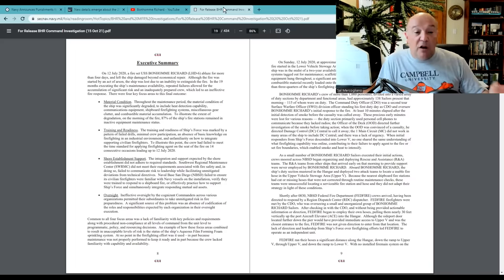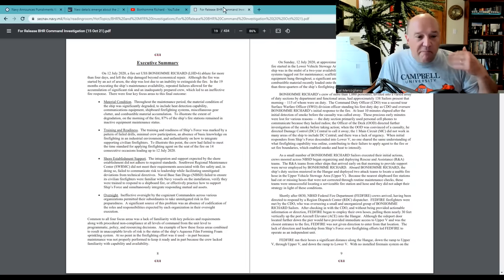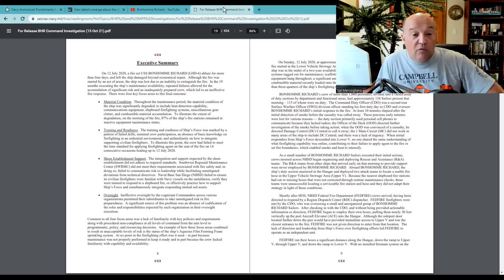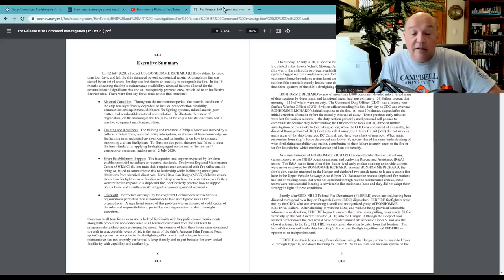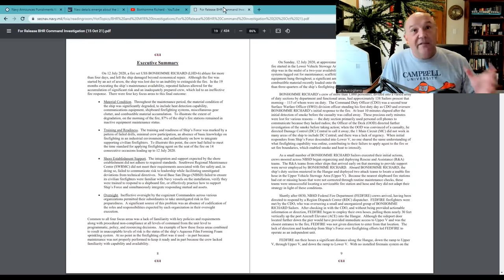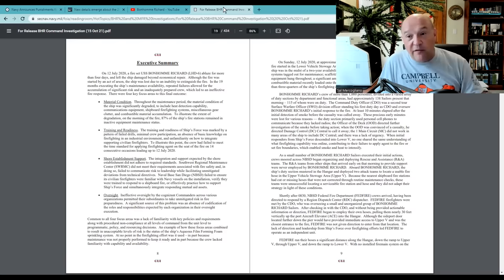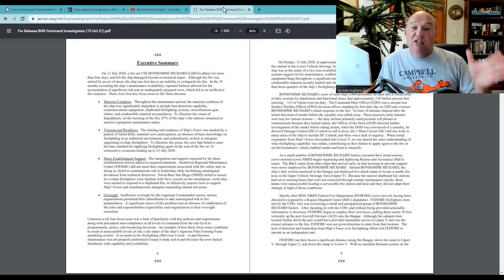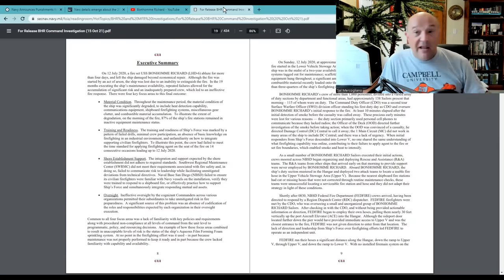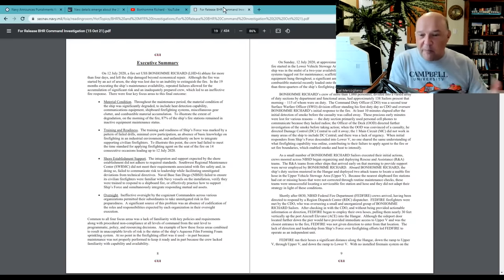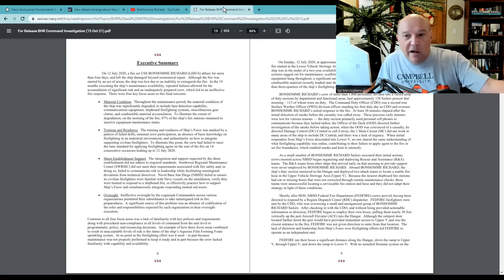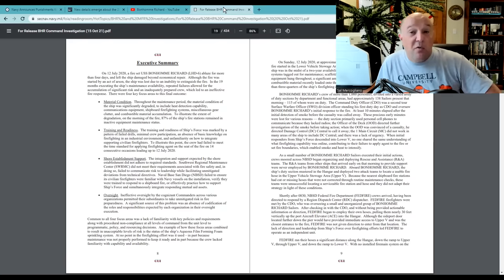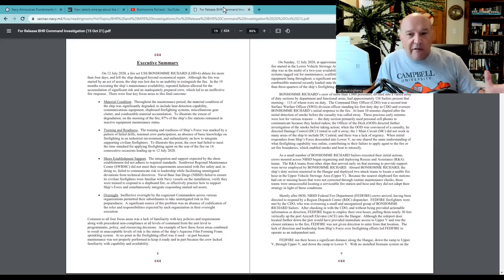Shore establishment support. The integration of the shore base with the ship failed on a massive basis. The Southwest Regional Maintenance Center did not meet the requirements associated with fire safety, and in doing so, failed to communicate risk to leadership while facilitating unmitigated deviations from technical directives. The Federal Fire Department didn't have adapters to connect their firefighting equipment to the ship's firefighting equipment, nor did they have provisions in place to lay fire hose from their rigs on the pier, their fire engines on the pier, into the ship. They didn't even have a fire main on the pier. They were on the pier. There was nowhere to hook up to for water on the pier. They had to lay in from hydrants thousands of feet away on land, down the pier, even though you're sitting above San Diego Bay.